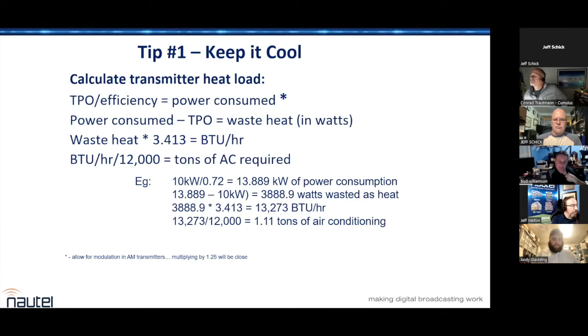If you're using forced air instead of air conditioning, and in this part of the world we can get away with that pretty well, make sure you move more filtered air into the building than you extract from it. That creates positive pressure, meaning you're leaking air out of every crack and crevice instead of sucking dust into every crack and crevice.